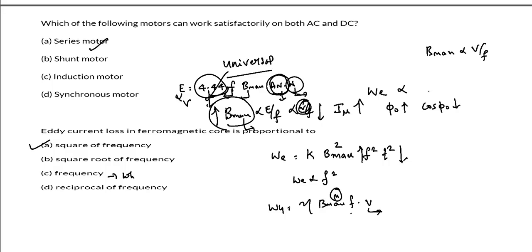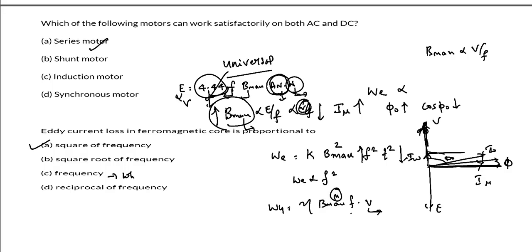You know very well about the transformer, so I need not explain all the things. This is the supply voltage. This is the flux; the induced EMF lags the flux by 90 degrees in a transformer. This is the magnetizing component of current. This is I_W, the core loss component of the current. So this is I naught. What happens if I keep the supply voltage constant and reduce the frequency? Bmax increases. Bmax is due to the magnetizing component of current, so that increases and this vector goes like this. What happens to phi naught? It increases, so the no load power factor decreases. Actually, the no load power factor is already low, and it still decreases.